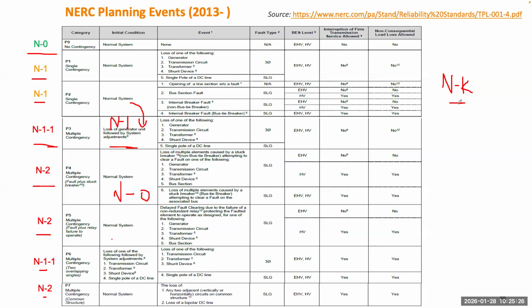study for N-K. But the total number of N-K scenarios can be huge, because if you think about any transmission grid, as we said, we have four interconnections. Right now we're in the Eastern Interconnection. Even though we're connected to the TVA power system, the TVA power system is tightly connected with the rest of the system in the Eastern Interconnection. If you bring up the Eastern Interconnection model, the bulk power system model has 70,000 buses or substations, including transmission and some sub-transmission. So N-K with K=1 means 70,000.